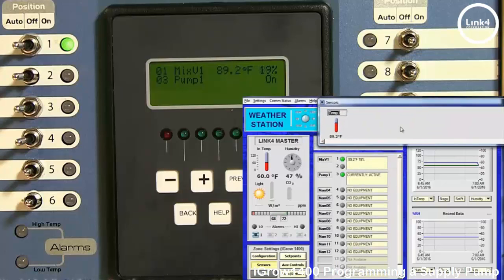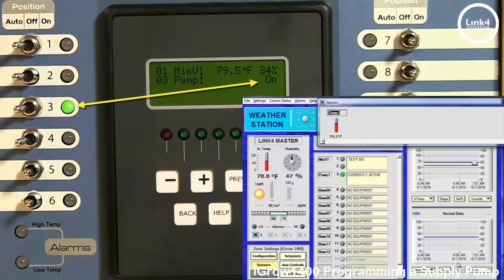and then we're going to take a look at our sensor and see what happens. And as you can see, the mix valve and the pump are in fact on, and with the temp probe being at 79.2, below the 80 degree threshold, the mix valve has opened at 33%. And the pump is active because it's open beyond the 5% threshold.